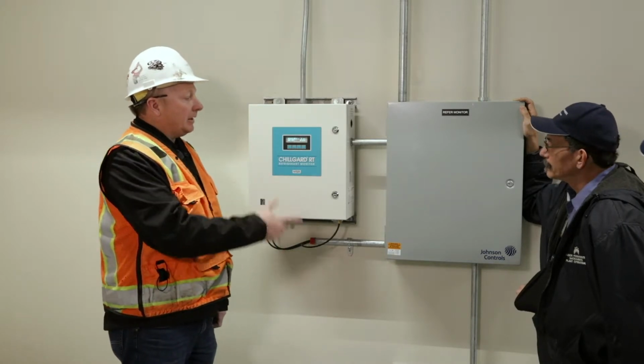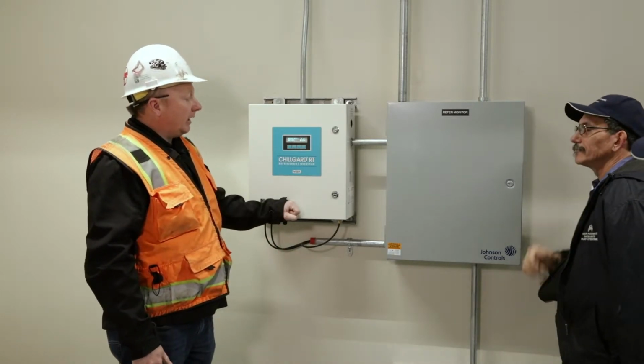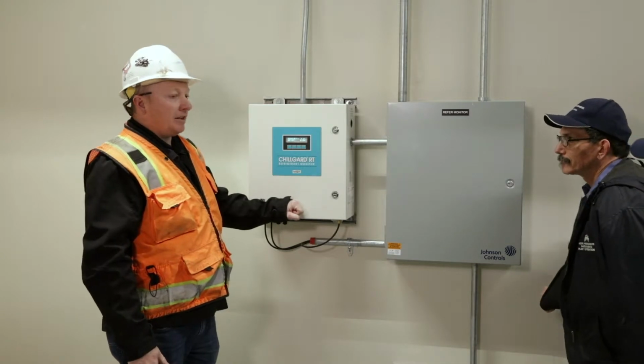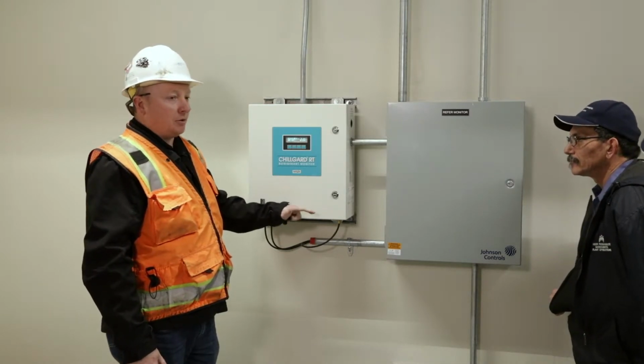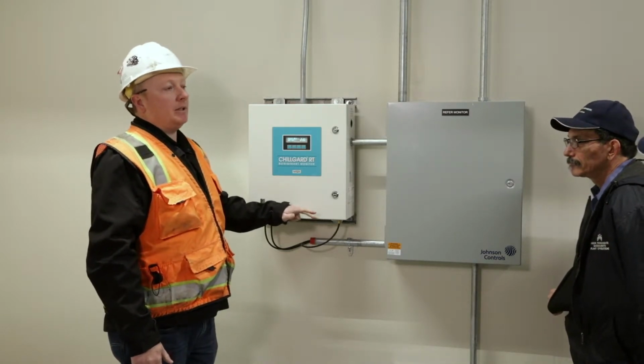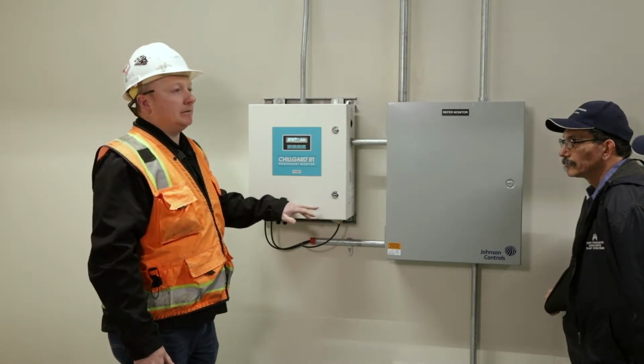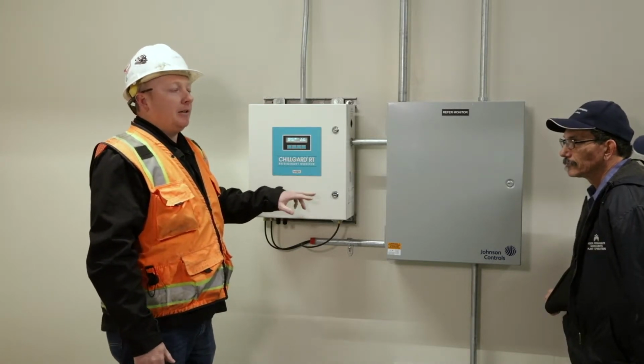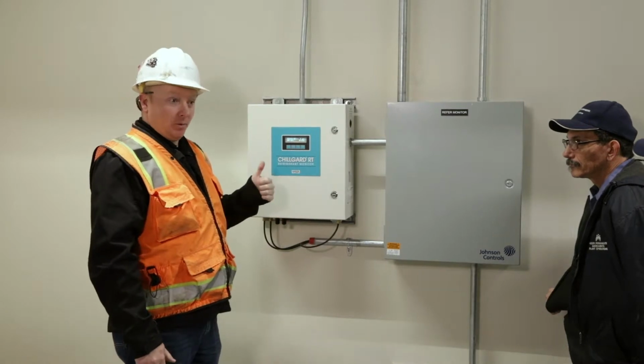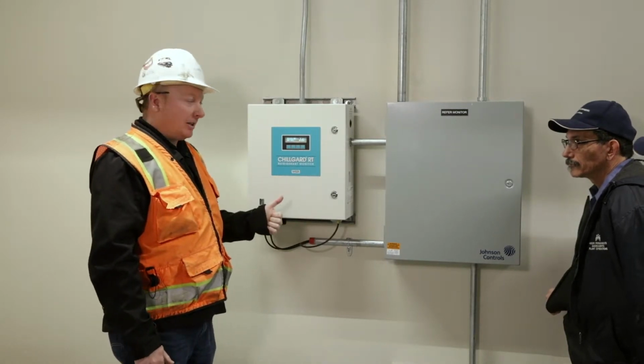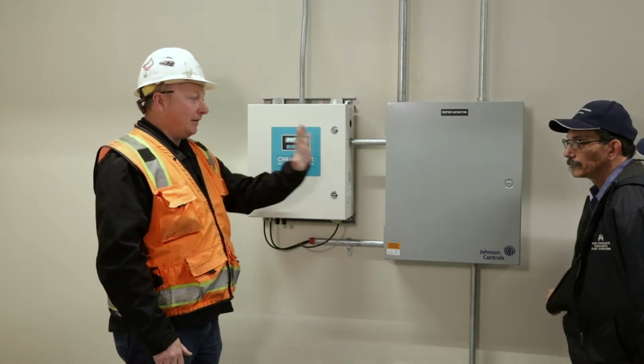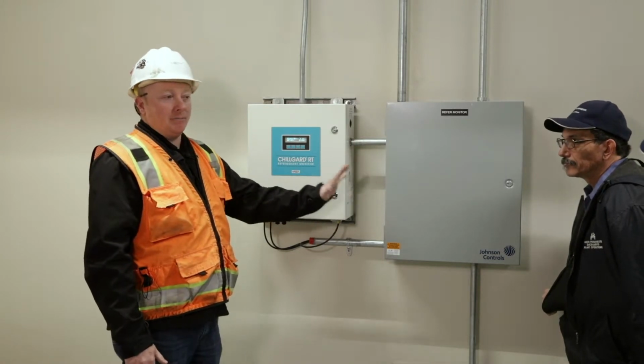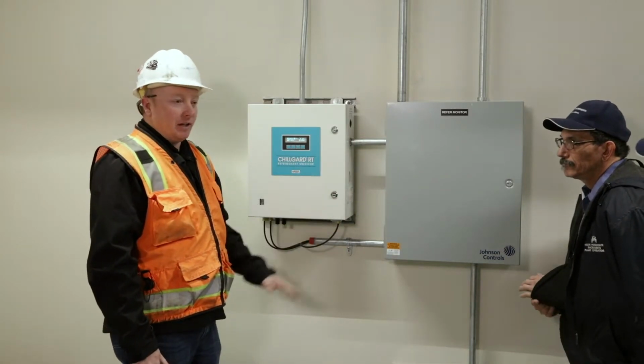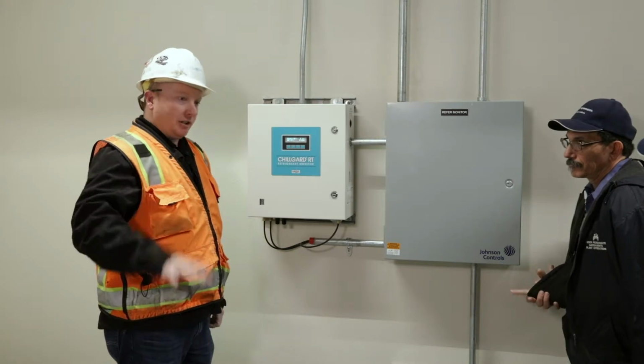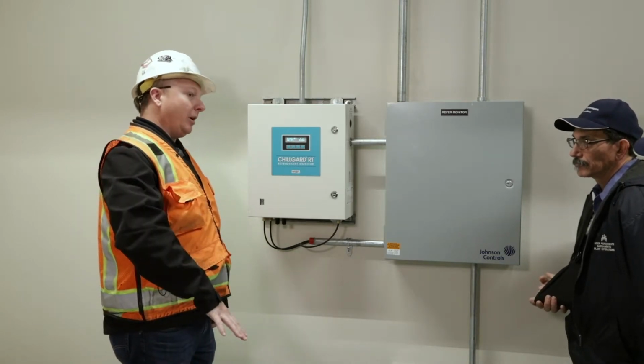Our panel next to it, we are monitoring 4 contacts off of this, I believe. Warning, trouble, alarm, and it might just be 3. They're all monitoring only except for the alarm contact. The alarm contact, if that closes on this, we recognize it over here. It triggers a whole sequence of events that'll basically shut down your chillers, shut down your pumps.